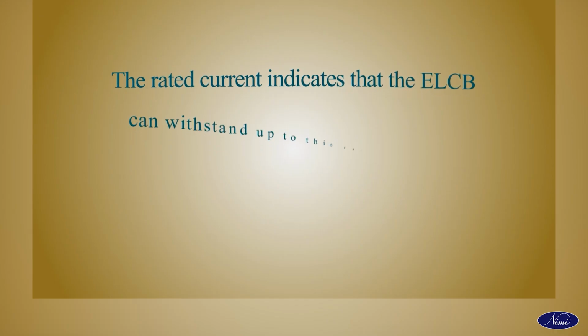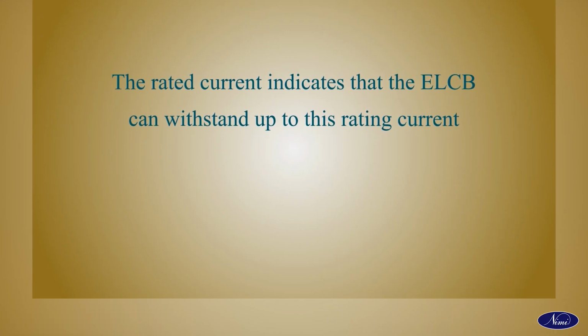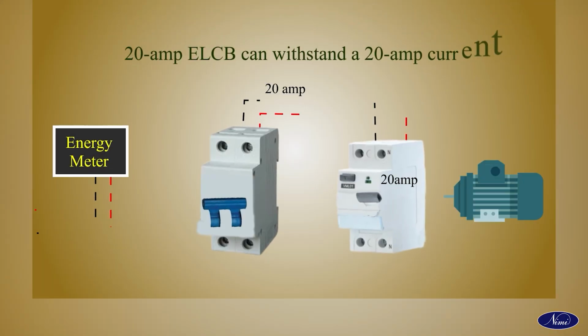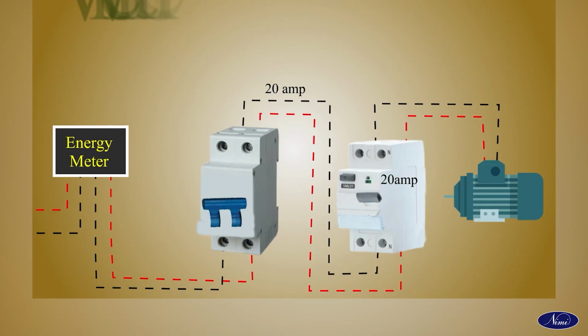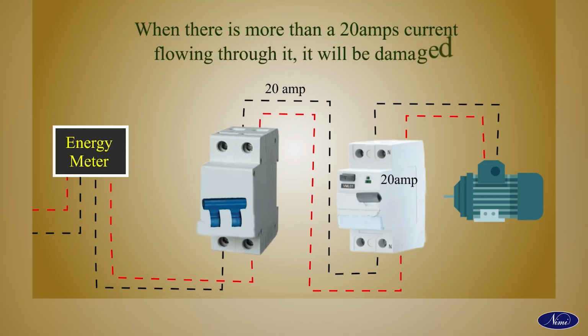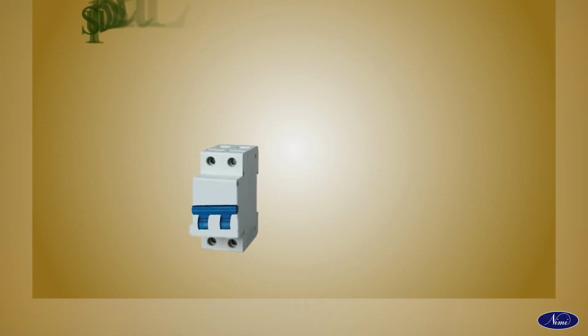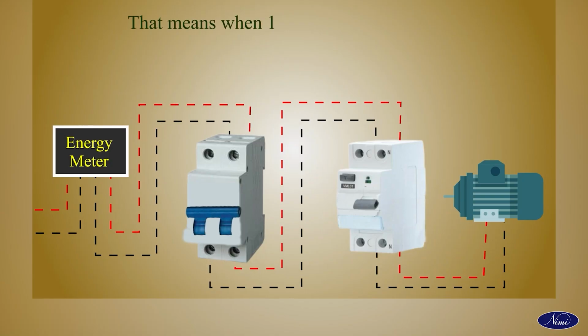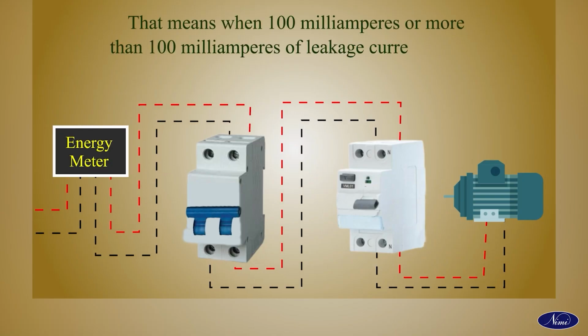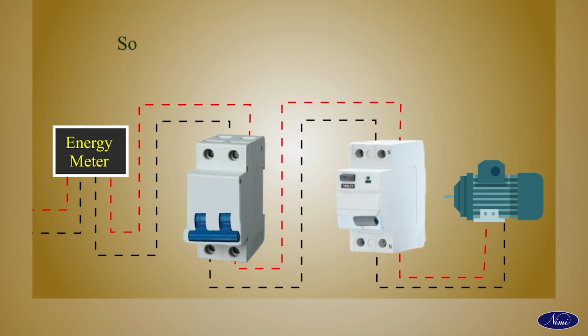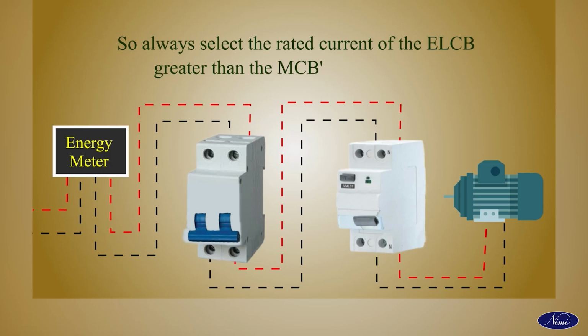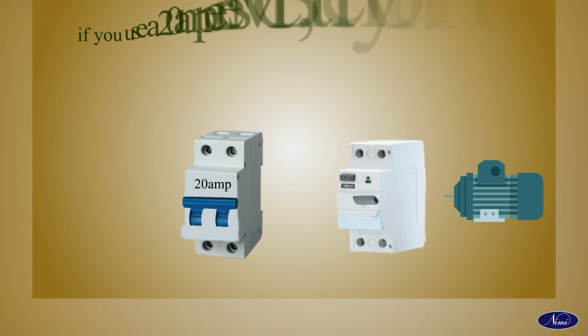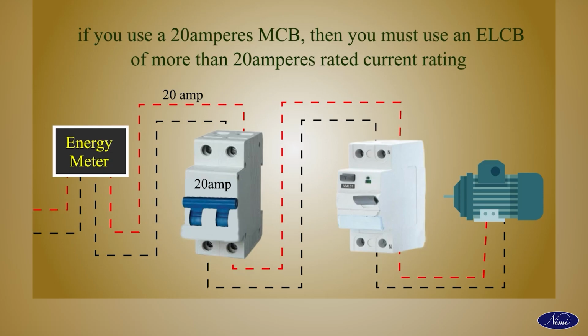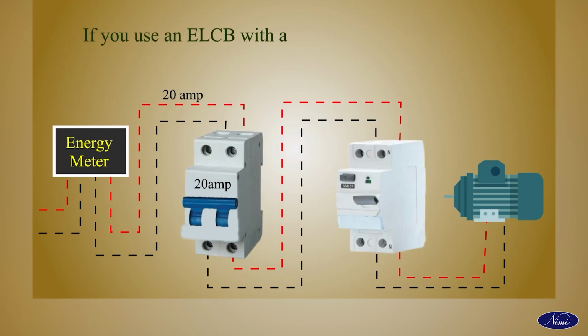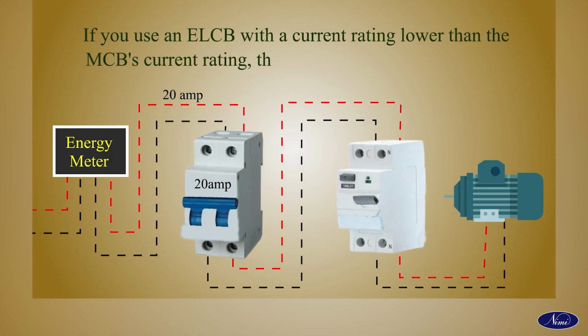The rated current indicates that the ELCB can withstand up to this rating current. For example, a 20 amp ELCB can withstand a 20 amp current. That means when there is more than a 20 amp current flowing through it, it will be damaged. Suppose an ELCB has a rating of 100 milliampere. That means when 100 or more than 100 mA of leakage current occurs, the ELCB will trip. So always select the rated current of the ELCB greater than the MCB's current rating. For example, if you use a 20 amp MCB, then you must use an ELCB of more than 20 amp rated current. If you use an ELCB with a current rating lower than the MCB's current rating, then the ELCB will be damaged.